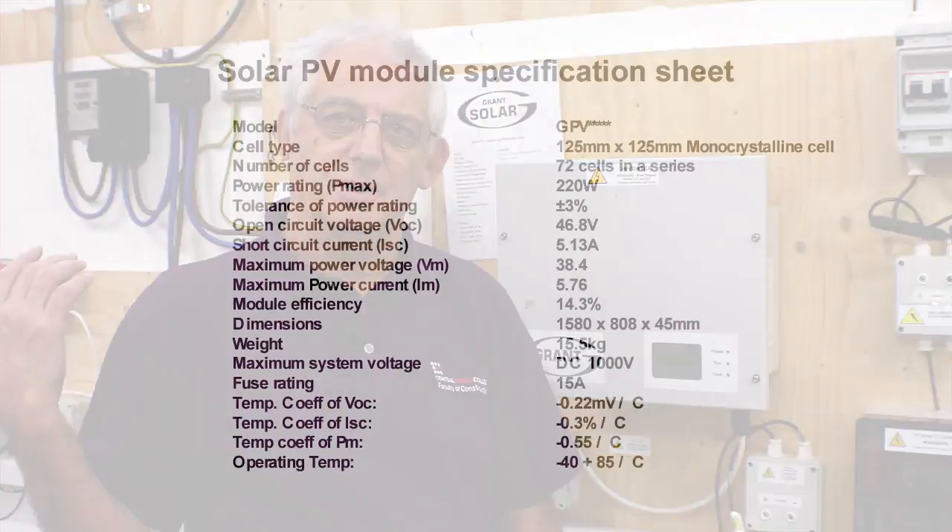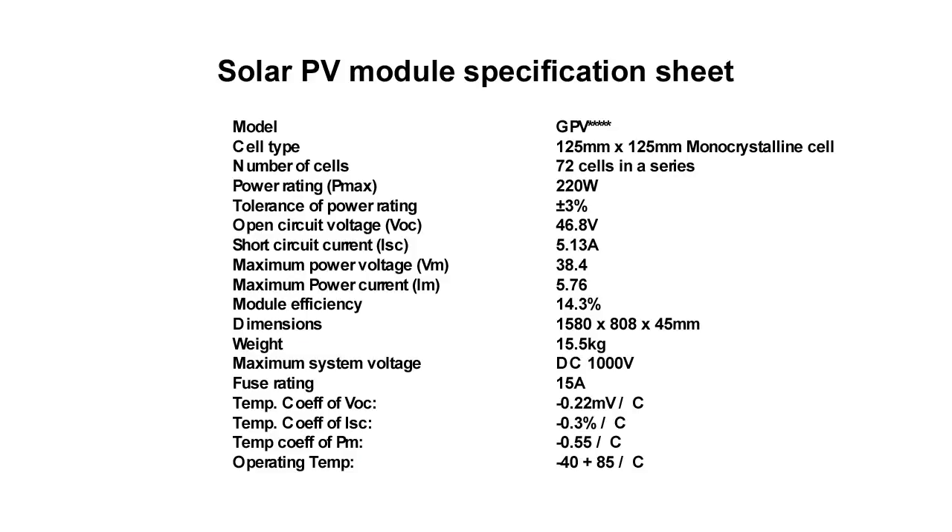To ensure our PV system is working correctly, we need to check the short circuit current to make sure that it coincides with the amount of sunlight we get. Our panels are rated at a short circuit current of 5.76 amps, which means they'll generate 5.13 amps when the sunlight is producing an irradiance of 1,000 watts per square metre.